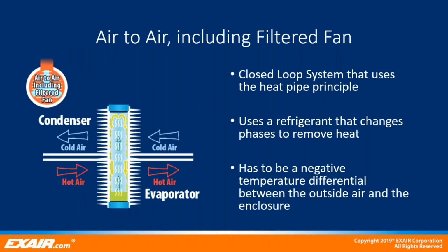So the first one we're going to talk about today is air-to-air, including the filtered fans. Heat pipes in an air-to-air heat exchanger cool enclosures by using evaporative cooling to transport thermal energy from one place to another via evaporation and condensation of a coolant. Heat pipes transfer heat through a phase change of a coolant, similar to a compressor-based conditioner, except they have no moving parts other than fans.